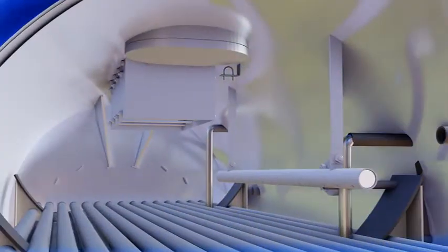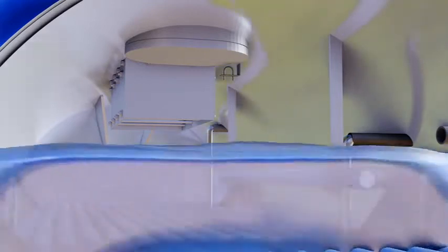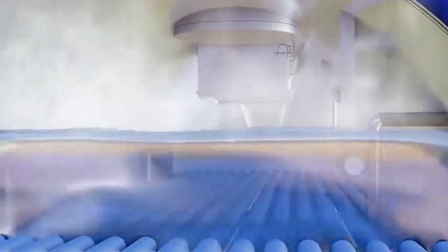The water-steam mixture moves up and returns back to the boiler shell through riser tubes due to buoyancy. Water Circulation Ratio is very important for the safe operation of the boiler. Lower circulation can lead to dry out and overheating of riser tubes. Fire tubes in the boiler shell also contribute in generation of steam. Separation of steam takes place at the topmost water surface, and the water level in the boiler drum is maintained by feed water pumps.